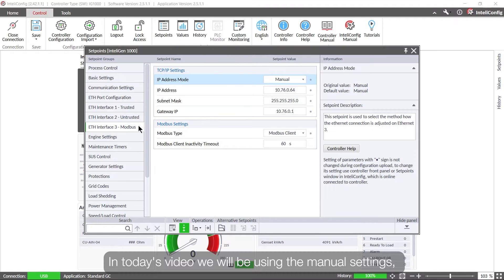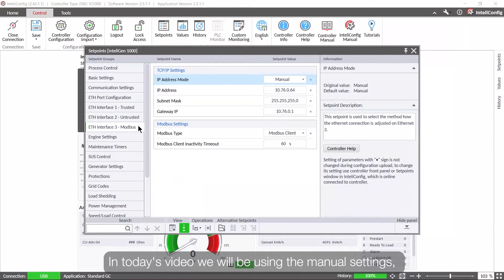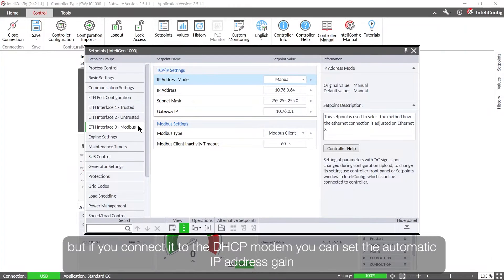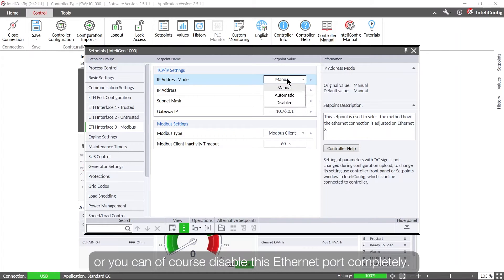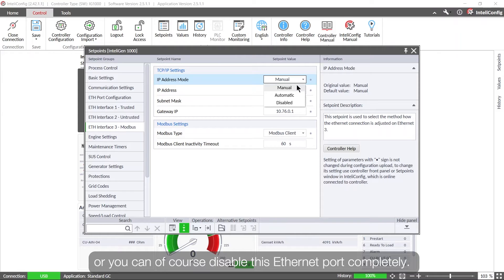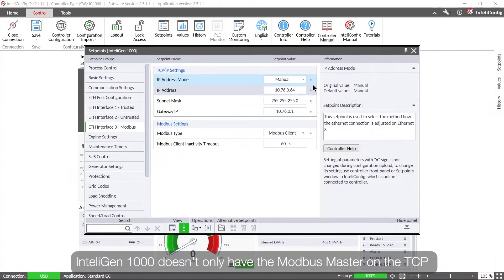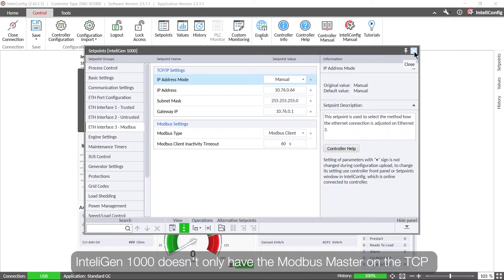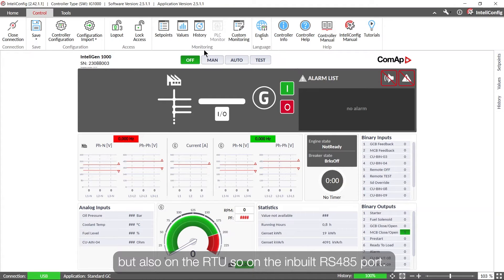In today's video we will be using the manual settings, but if you connect it to the DHCP modem you can set the automatic IP address gain, or you can of course disable this Ethernet port completely. InteliGen 1000 doesn't only have the Modbus master on the TCP but also on the RTU, so on the inbuilt RS485 port.